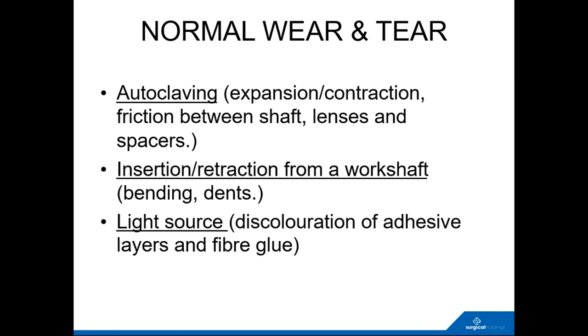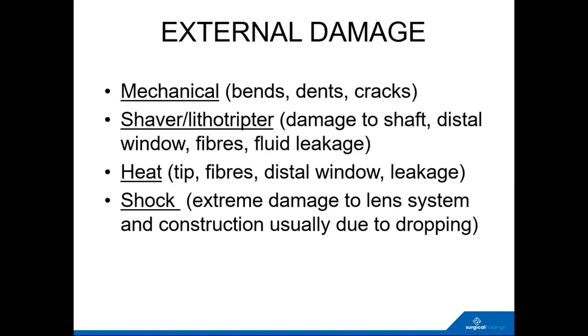Insertion and retraction from the shaft, particularly if the shaft is damaged, can lead to problems with the endoscope. And the light source, using an inappropriate light guide. A classic one would be a light guide for a large scope on a small scope. You're getting too much power from the light and you'll get problems. That is something that we've seen quite often. Light guide cables may get mixed up, and they're generally all quite slim in diameter anyway, so it's easy to mix them up and make that mistake. So it's certainly worth double checking that, because that can be potentially very hazardous from a heat perspective.